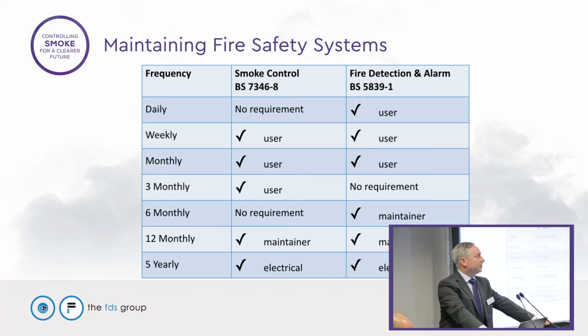The weekly check is probably the one that everyone's familiar with, the fire alarm test. You press the button on the wall and the bells ring, and sometimes you stay put and other times you run out of the building. In terms of smoke control, what we're looking for there is that the system activates. Nothing more, just that when you activate the fire alarm system or fire detection system, the system fires up. If it's mechanical, that the fans start up and start extracting on the fire zone. If it's a natural system, that the AOV would open. Under a monthly test, this is a bit more comprehensive now.